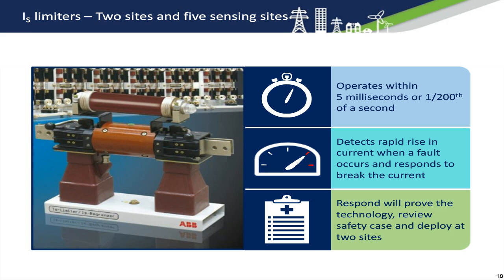When enabled by the fault level assessment tool, the IS limiter will monitor normal current flowing through it. When a fault occurs, the IS limiter detects the rapid rising current and responds by setting off a small explosive charge which breaks the normal flow of current. This removes some of this fault current flowing through our at-risk asset equipment and allows it to operate safely.